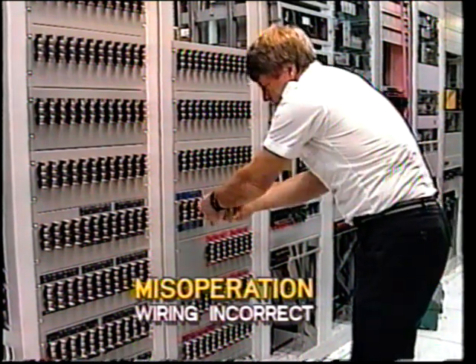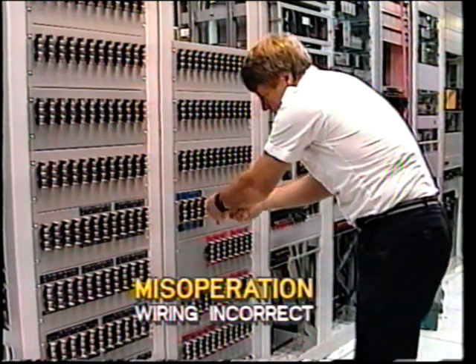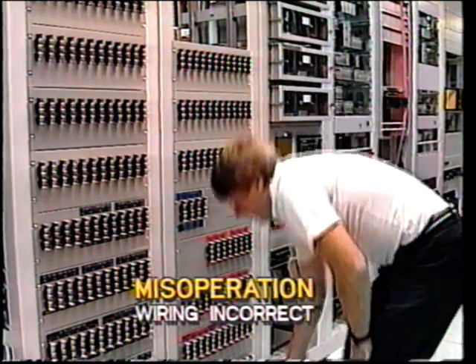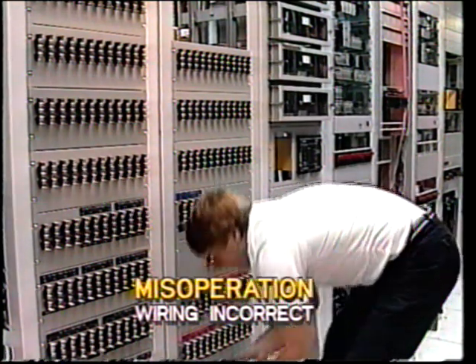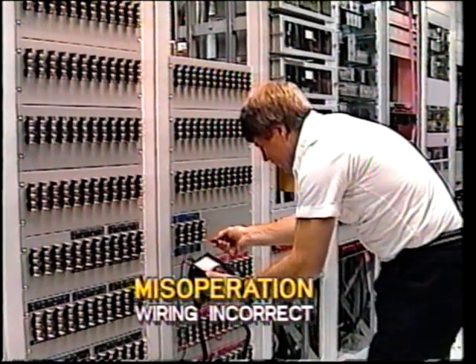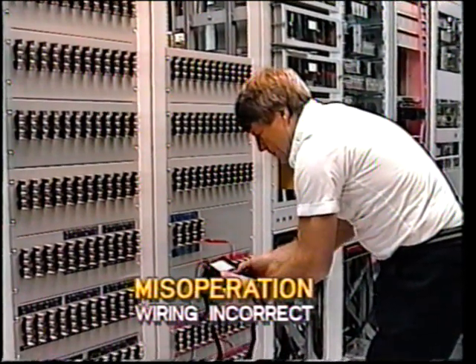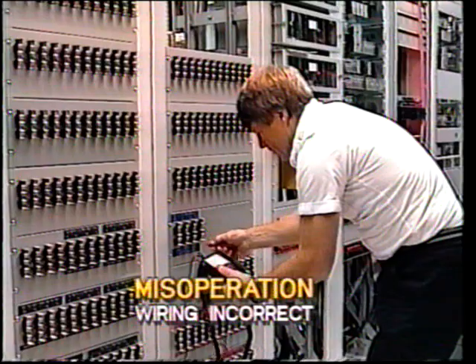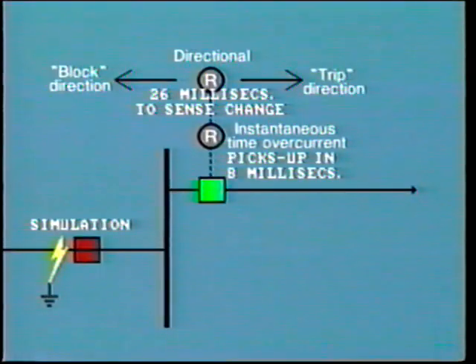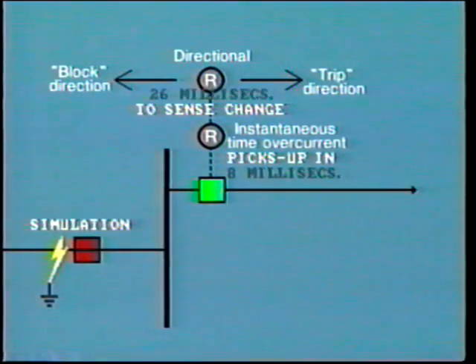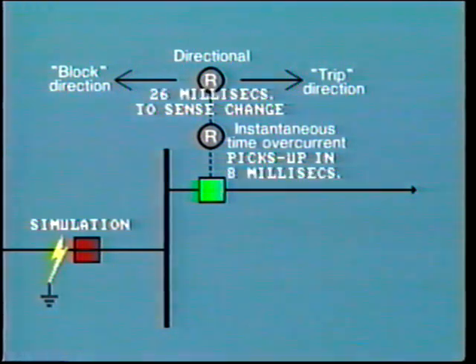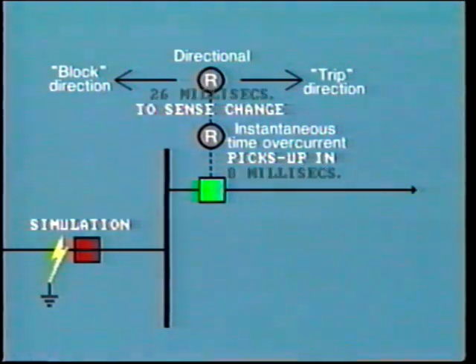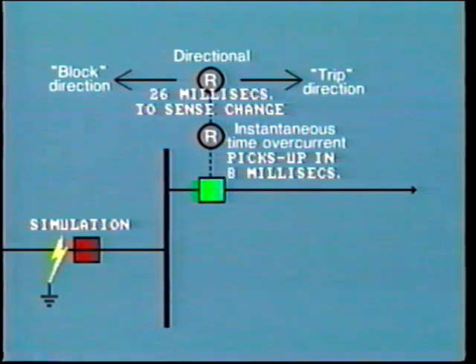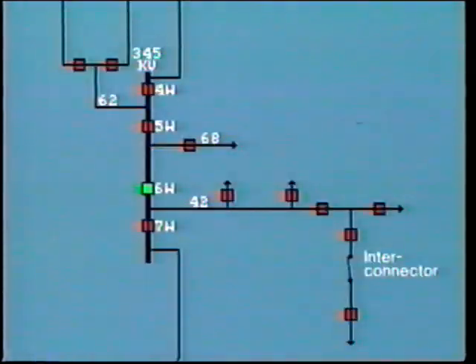First, the wiring was incorrect. This should have been detected by in-service load tests during the commissioning stage, even though the manufacturer's information itself was incorrect. So we have manufacturer's error. We also have a design error because this particular combination of directional unit and instantaneous unit allowed false tripping. Apparently, this installation needs a faster directional unit. Now let's take a look at another example.